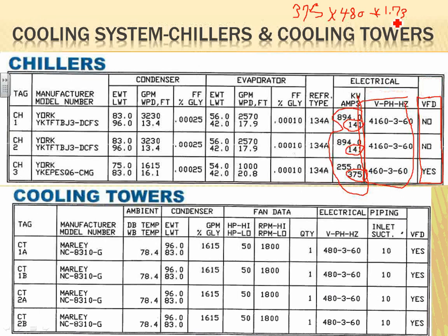But the manufacturers of this equipment will also give you a minimum circuit ampacity that you have to use anyway. It's already done for you. So for everything we've done today, the only new stuff is just the chillers. The cooling tower as well as the pumps are all motor loads, and what we did last week in terms of the sheet that I shared with you applies to the cooling tower, the air handling unit, as well as the pumps in between, because they're all motors. So the special part is really the chillers here.